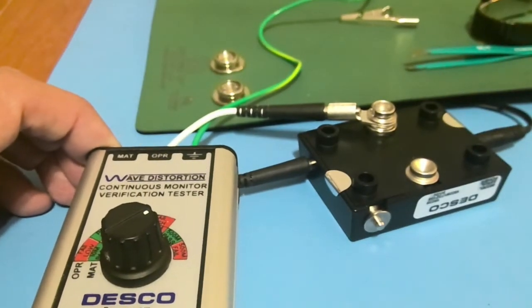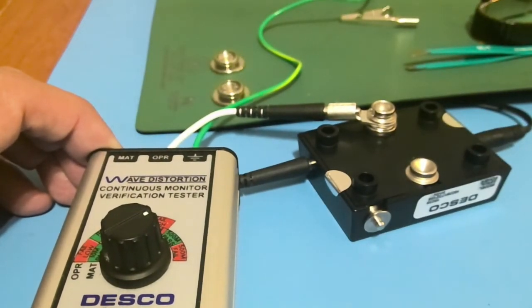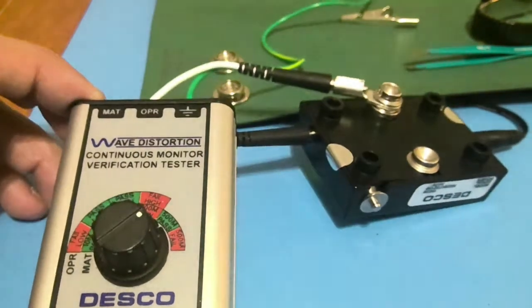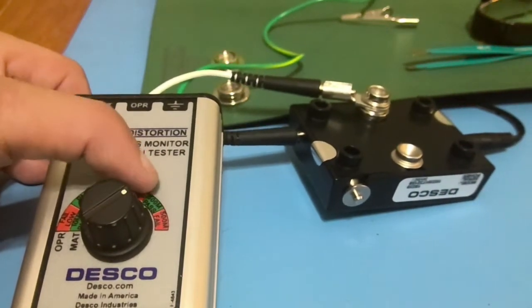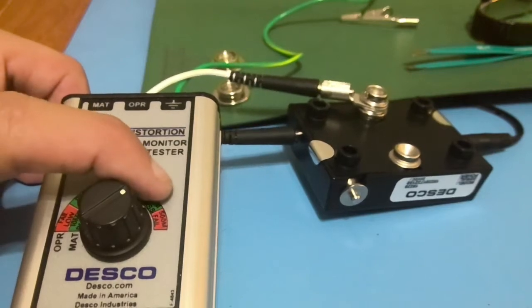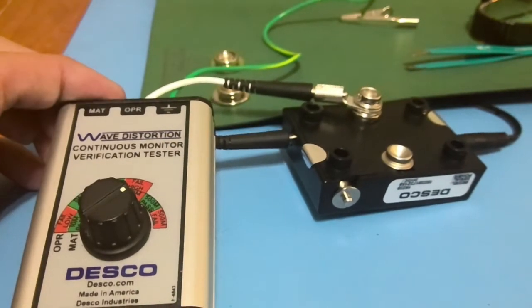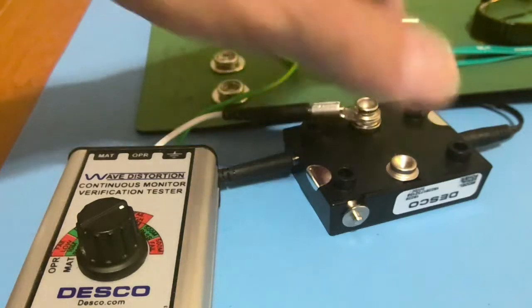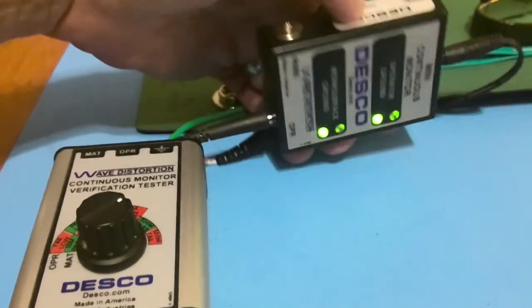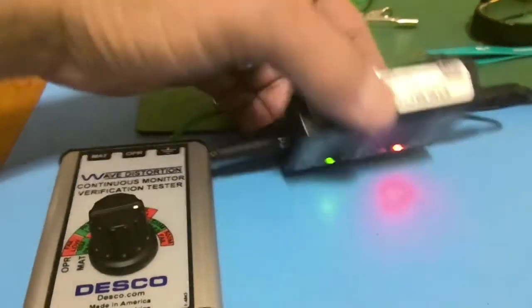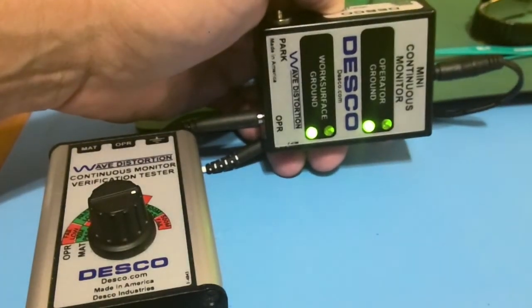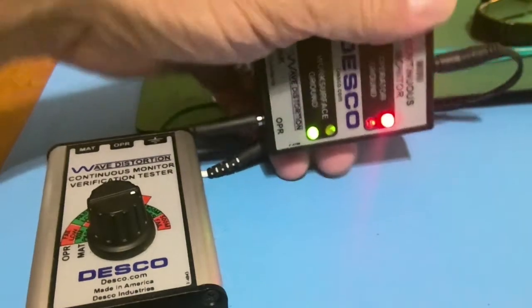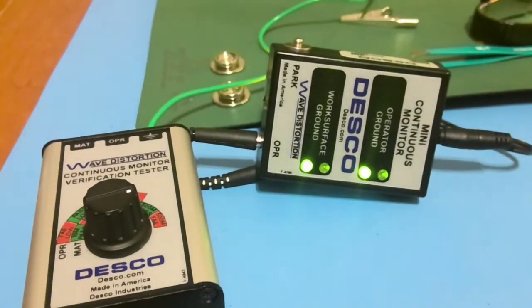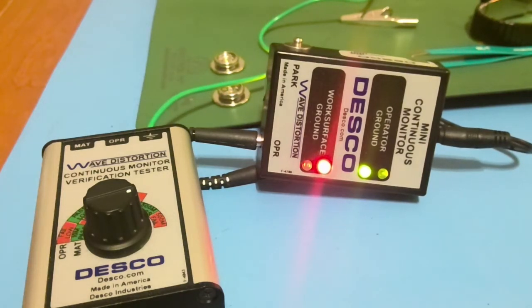They send you all the hardware you would need. Alright, so same thing's going to happen here, only this time if you looked at the instructions, there's only 2 tests you have to do, and they're over here: 500 meg pass, 500 meg fail. Those are the only 2 tests you have to do, and you'll notice right now I'm on 500 pass and I got all green lights. If I switch to 500 fail, it'll take just a second. Maybe I should take my hands off of it. It will show that the work surface is failing.